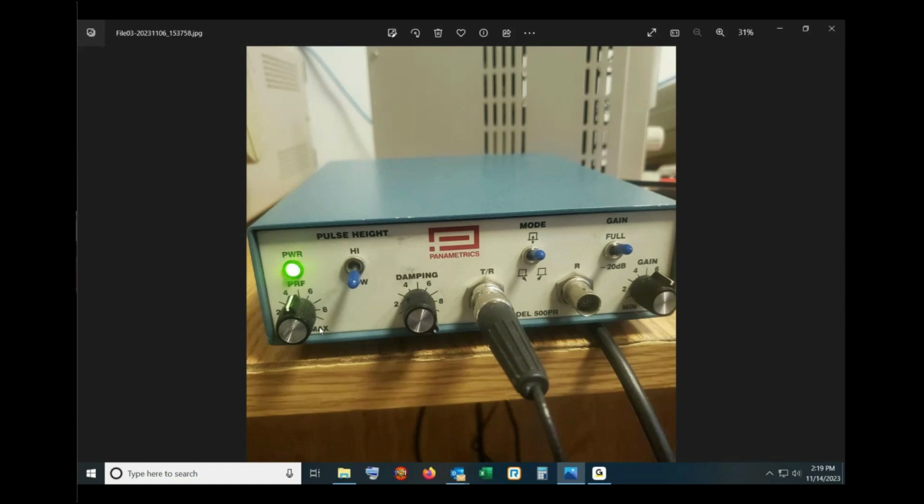So that's the pulse repeat frequency. So typically in ultrasonics, you're sending an excitation, listening to the echoes, but you're not just doing that once. You're doing that over and over and over again, in between which you might be moving your ultrasonic transducer across a sample, maybe in a two-dimensional grid, so that you can actually get an image of the material. So you could imagine going over a material the way you would mow a lawn in order to get everything, and then color coding the positions of cracks in that slab, let's say, so that you could localize any cracks positionally, if you see what I mean. So typically you're not just acquiring one waveform, you're acquiring multiples and turning it into an image.